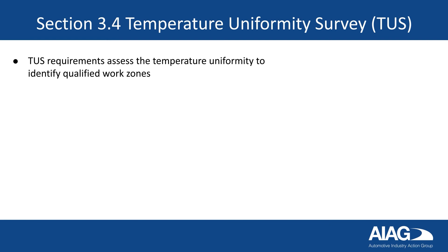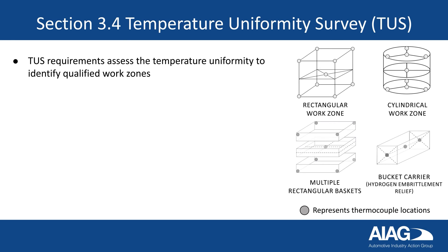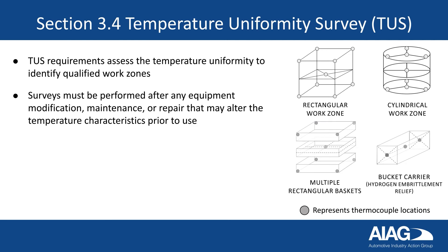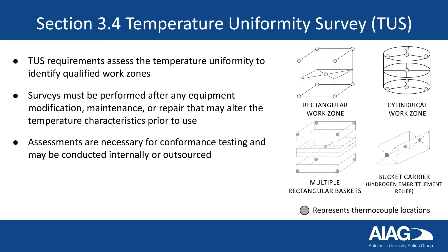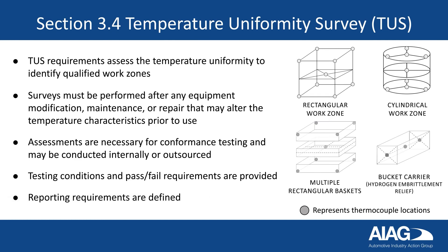Section 3.4 describes the use of a temperature uniformity survey to identify qualified work zones. Thermocouples are placed strategically throughout the work zone to validate the uniformity of the temperature. Surveys must be performed after any equipment modification, maintenance, or repair that may alter the temperature characteristics prior to use. These assessments are necessary for conformance testing and may be conducted internally or outsourced.